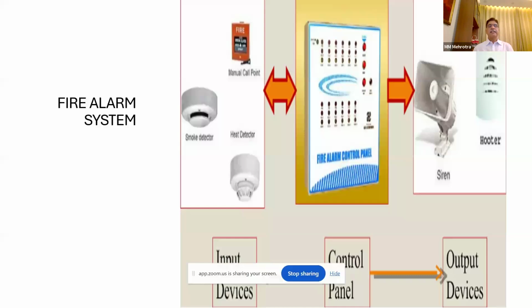Below that, that means there is no fire or fire is controllable. But when the fire has spread, the temperature in that vicinity will reach that level. Then your heat detector will operate and set supply to my output devices. Output devices I will come to.